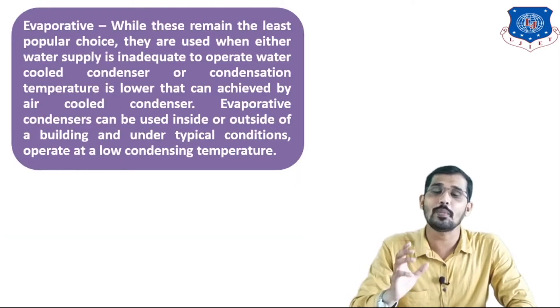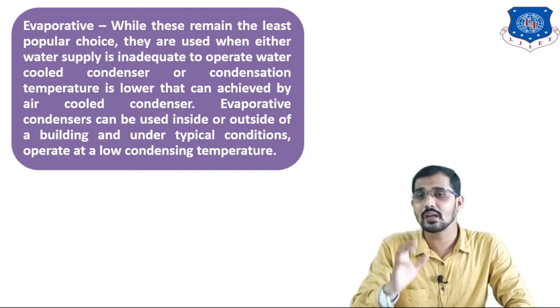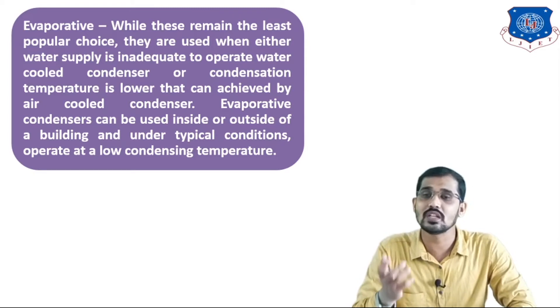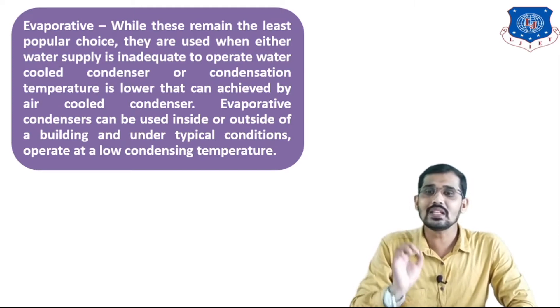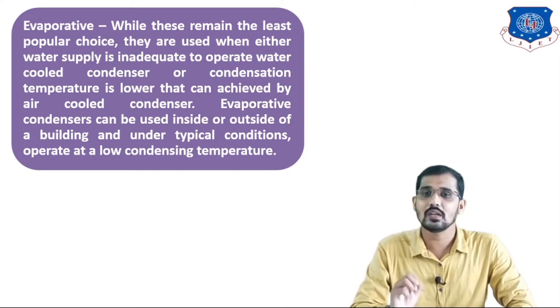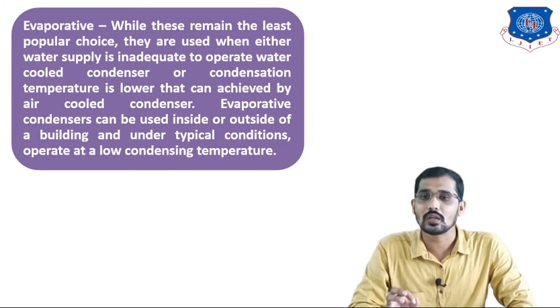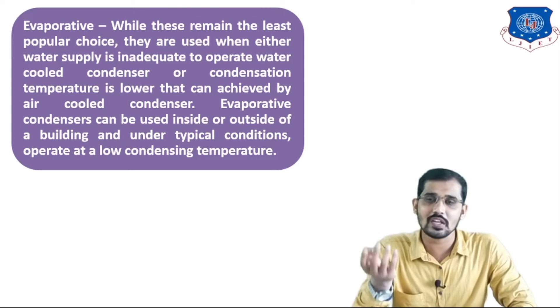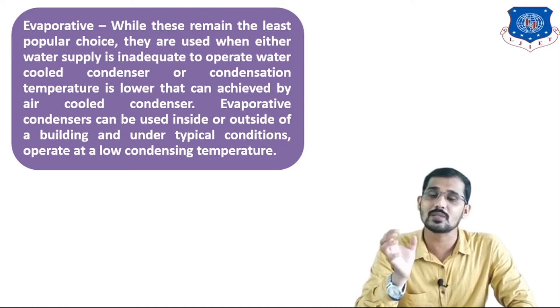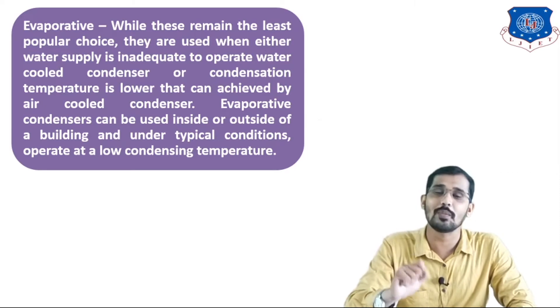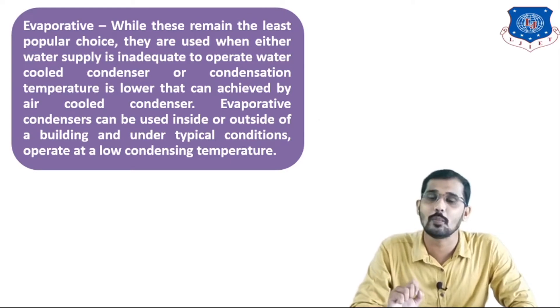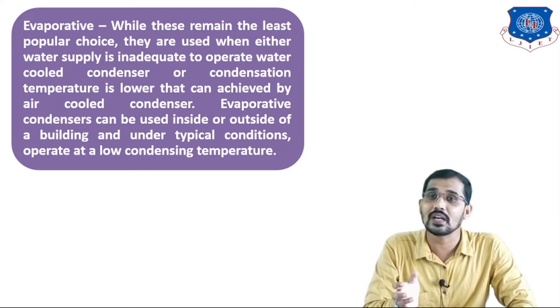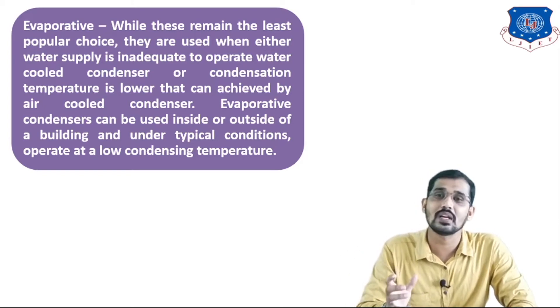The last one is the evaporative condenser. The limitations available in both air cooled and water cooled condensers can be overcome with the evaporative condenser. These remain the least popular choice, but they are used when either the water supply is inadequate to operate a water cooled condenser, or the condensation temperature required is lower than what can be achieved by an air cooled condenser. This evaporative condenser can be operated at different temperatures, and its major applications are at lower temperatures.